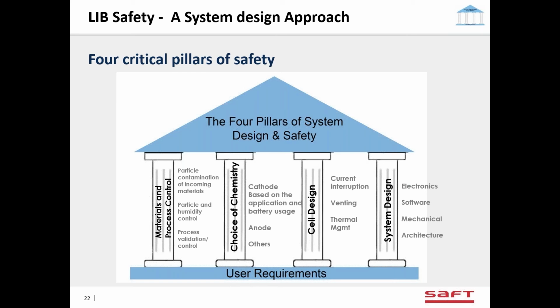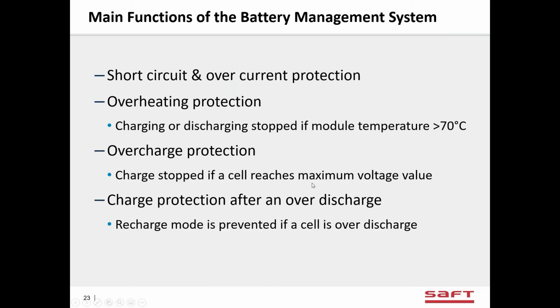The last piece is system design. With lithium-ion batteries, you have to measure every cell voltage, measure the current, and measure the temperature. You have to have software monitoring all of that, and you have some controls to take the battery offline if it's going to go into thermal runaway, though we stop way before then. If it gets too hot, we can disconnect the battery. Actually, I can go to my next slide. These are the main functions of the battery management system.